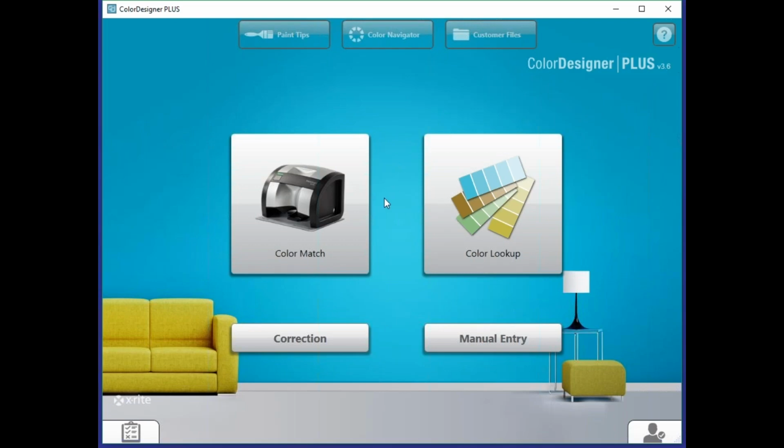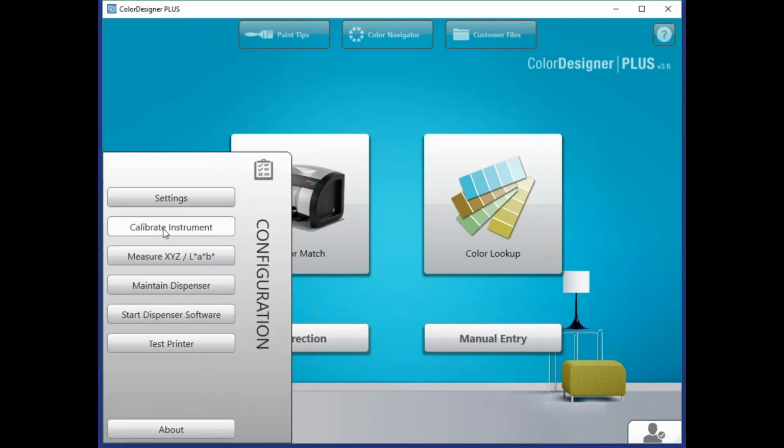But the first thing with the instrument is the calibration. And with that, you're going to calibrate every day. There's an indicator light on the instrument, as you've seen. It's a red light, meaning it needs calibration. Green light means it's calibrated and ready to go. This happens on a 24-hour basis. We can set the software up to calibrate when you want it to. So again, features inside there. But again, this is for those of you that have it. I want to make sure I talk and walk through some of the features inside.